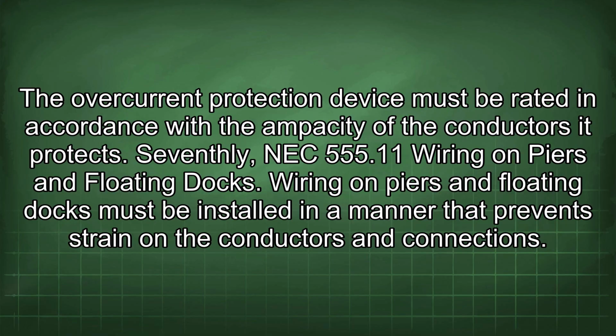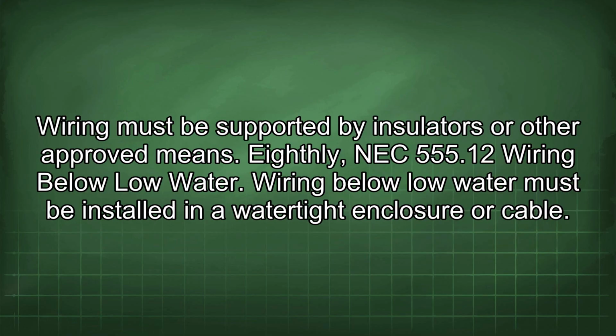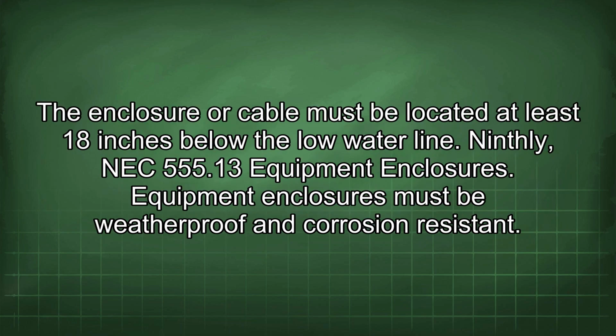Seventhly, NEC 555.11 Wiring on piers and floating docks. Wiring on piers and floating docks must be installed in a manner that prevents strain on the conductors and connections. Wiring must be supported by insulators or other approved means. Eighthly, NEC 555.12 Wiring below low water. Wiring below low water must be installed in a watertight enclosure or cable. The enclosure or cable must be located at least 18 inches below the low water line.